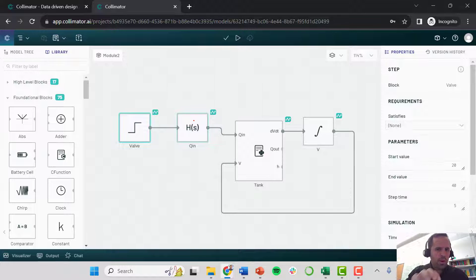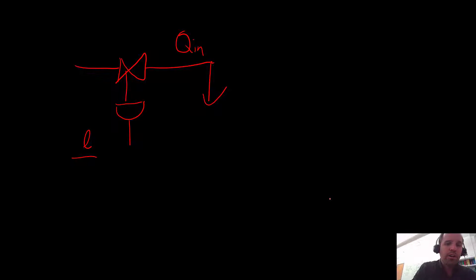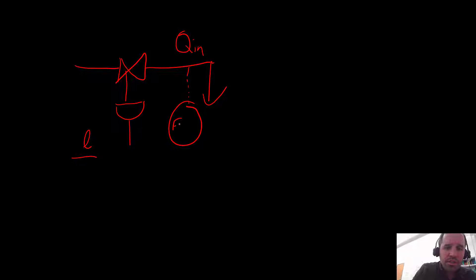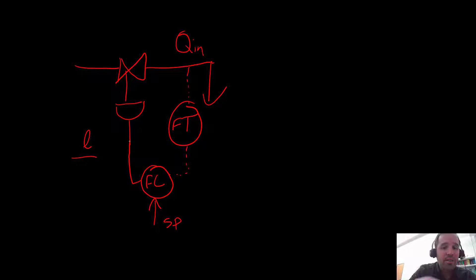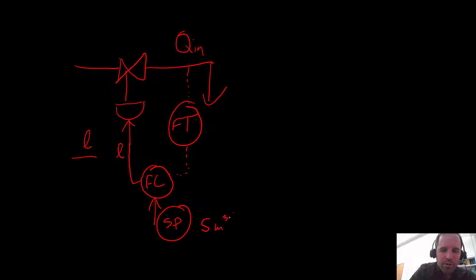Instead of specifying valve position, we want to tell our system we want a particular flow rate — say five cubic meters per minute. The answer is to add a controller. Specifically, we would first measure our flow rate using something like a flow transmitter. We'd send that signal to a flow controller, which takes in a set point. Once it has the set point, it pushes a command — our lift or valve position — to the actual valve. So we'd give it a set point of something like five cubic meters per minute.